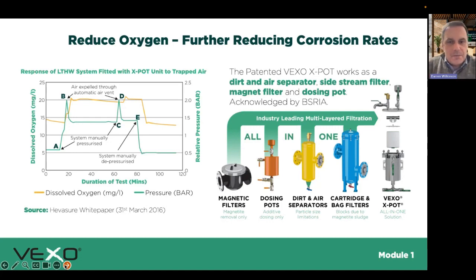Obviously, in a closed loop system, not so straightforward. So the only way to do that is through pressure step degassing, where we put a volume of water at a time through a cylinder and reduce the pressure in that vessel for a moment in time, which releases dissolved gases, and we can then send that water back into the system. But that does take time. You're only doing so much, but over a long period.